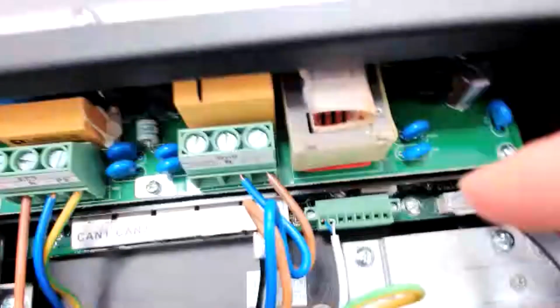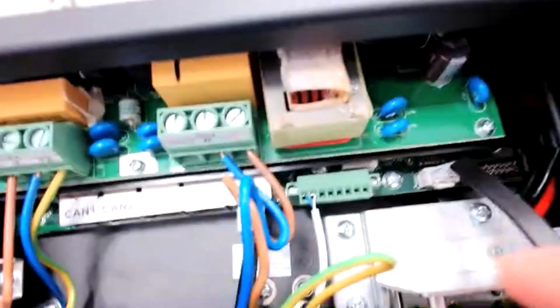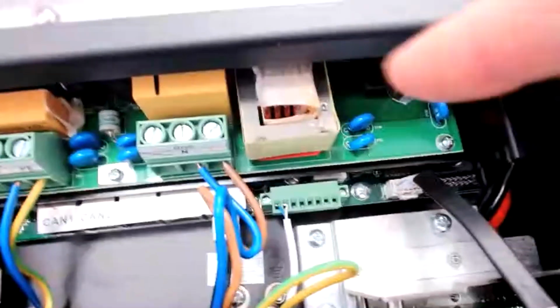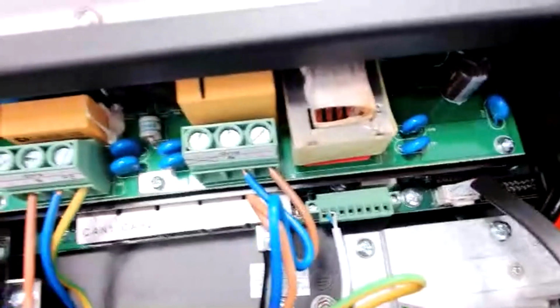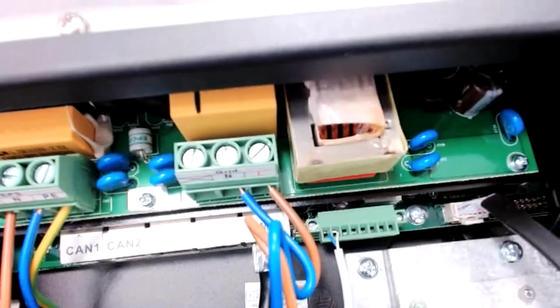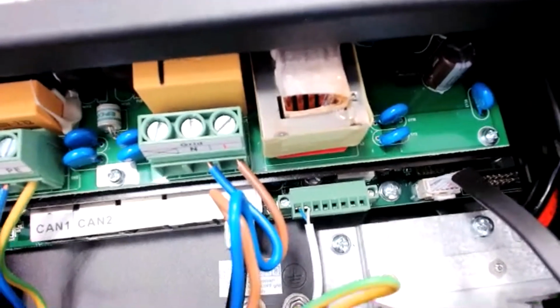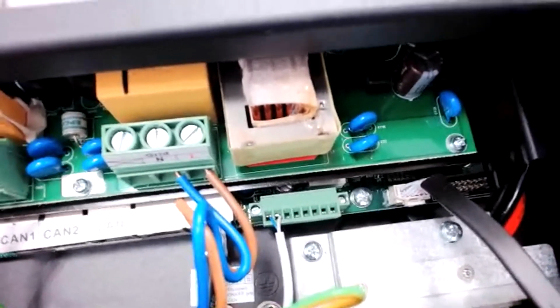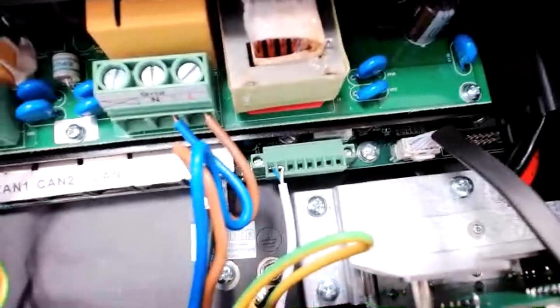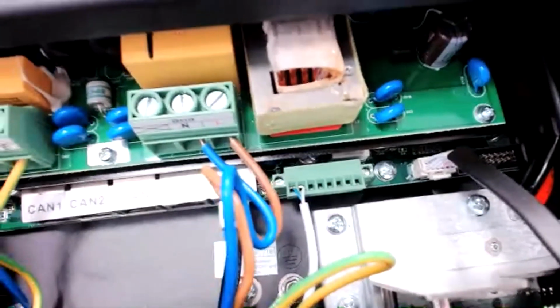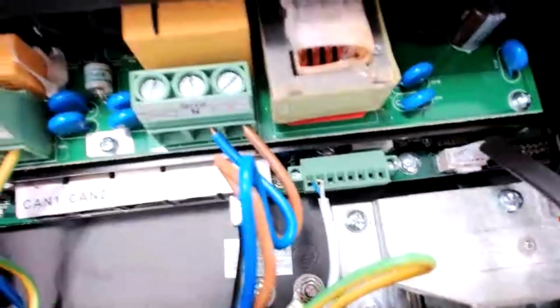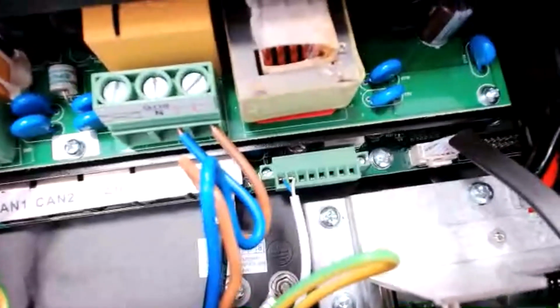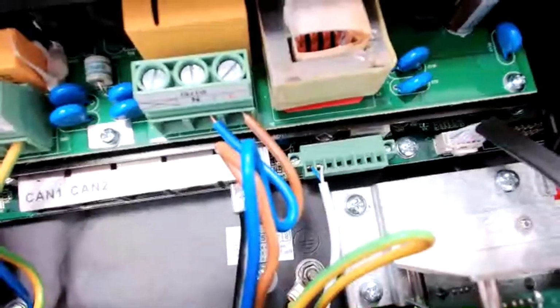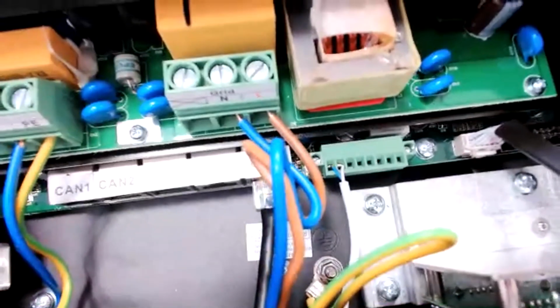The same thing will happen when you connect the meter, when you don't connect the meter, or when you just confuse the pins with each other. It will immediately say CT failure, and then you can look that up. Basically, when you have the CT failure, it's either the connection is not properly done or the pins are switched. But it's really easy to solve this problem.